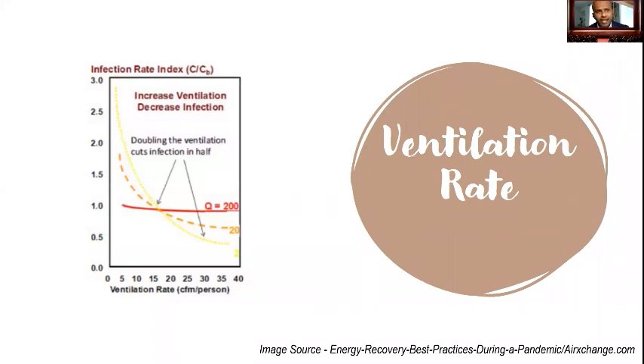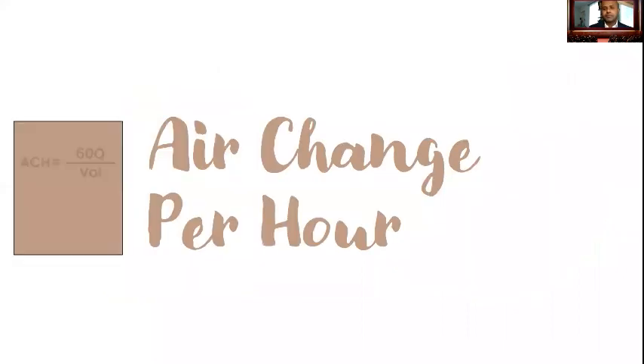Using the Wells-Riley equation, doubling ventilation rates has the potential to reduce infection rates by half. An air exchange is how many times the air enters and exits a room from the HVAC system in 1 hour. In other words, it is a measurement of how many times a volume of air within a room will be added, removed, or exchanged with filtered clean air.